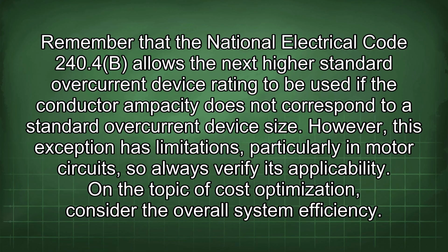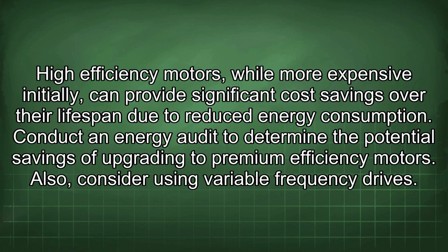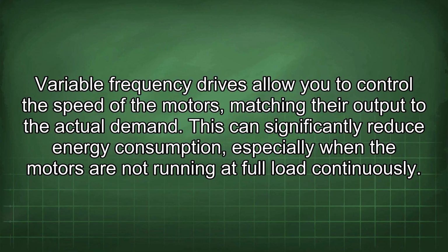On the topic of cost optimization, consider the overall system efficiency. High-efficiency motors, while more expensive initially, can provide significant cost savings over their lifespan due to reduced energy consumption. Conduct an energy audit to determine the potential savings of upgrading to premium efficiency motors. Also, consider using variable frequency drives. Variable frequency drives allow you to control the speed of the motors, matching their output to the actual demand. This can significantly reduce energy consumption, especially when the motors are not running at full load continuously.